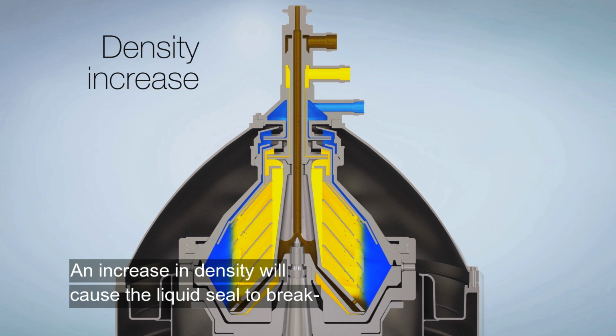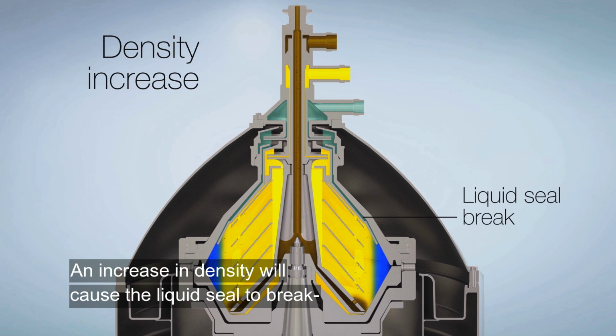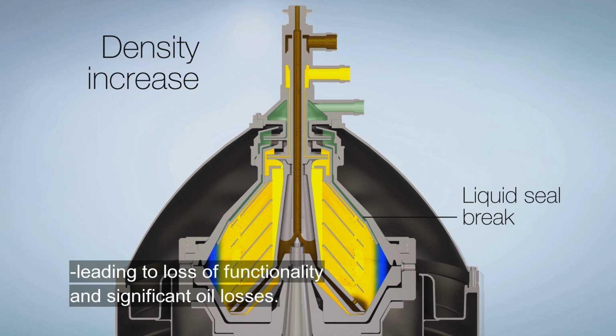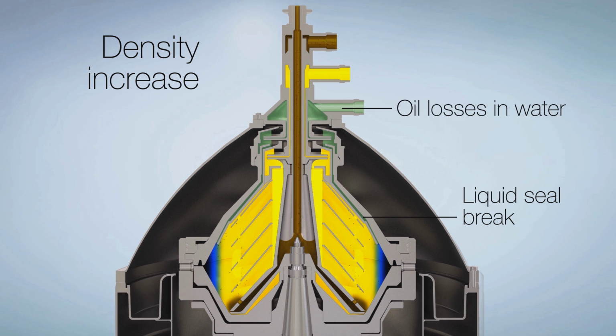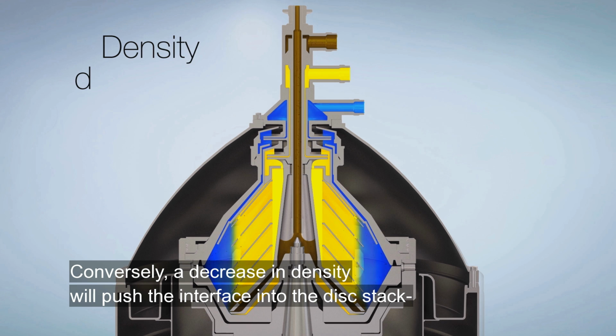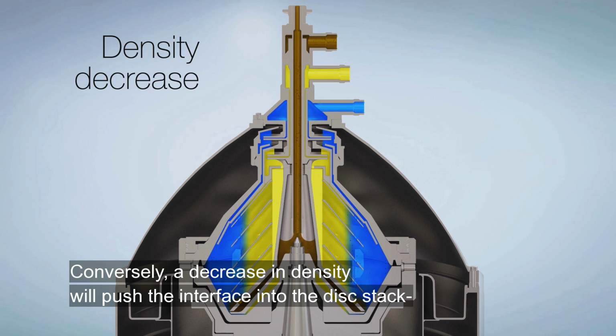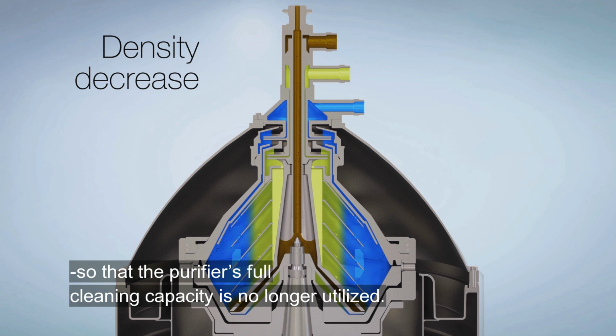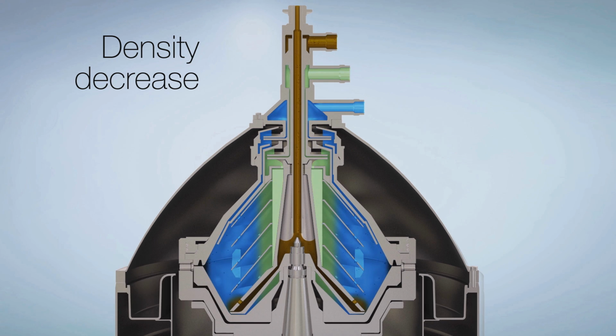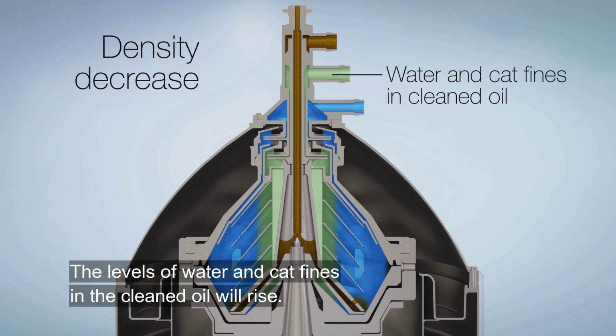An increase in density will cause the liquid seal to break, leading to loss of functionality and significant oil losses. Conversely, a decrease in density will push the interface into the disc stack so that the purifier's full cleaning capacity is no longer utilized. The levels of water and cat fines in the cleaned oil will rise.